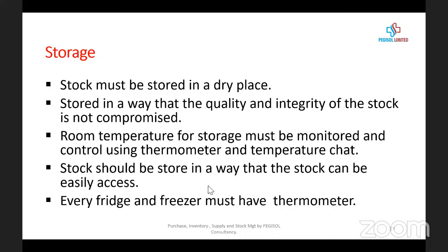So please take note and write: every fridge and freezer must have a thermometer. Type it on the chat box, just so I'm sure you are with me and hearing. Yes, thank you, I can see that. Every fridge and freezer must have a calibrated thermometer. How often must it be calibrated? Minimum yearly, at least once in a year.